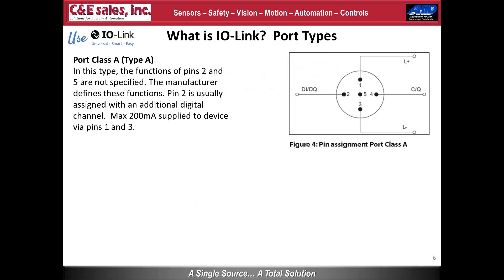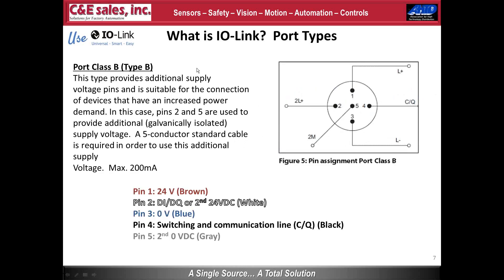There are two port types in IO-Link. Port Class A has power on pins 1 and 3, the IO-Link channel on pin 4, and sometimes an additional digital input on pin 2. Port Class B uses pins 2 and 5 for an additional power supply, typically used for valves and devices requiring extra power.